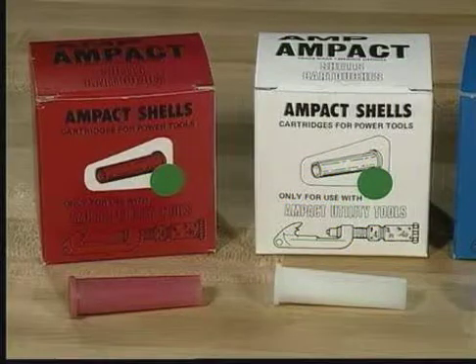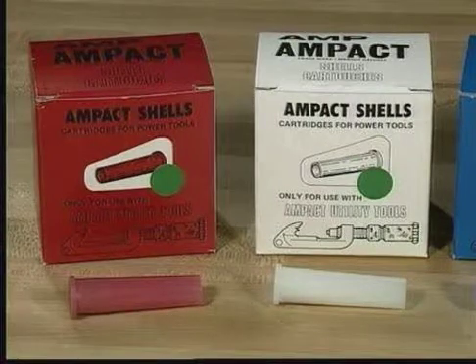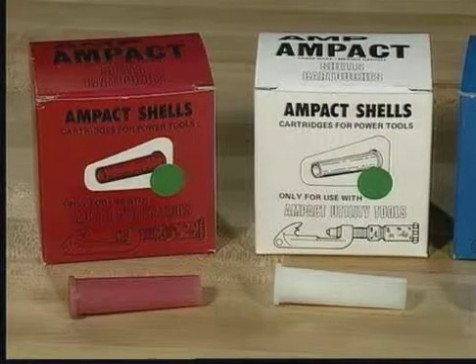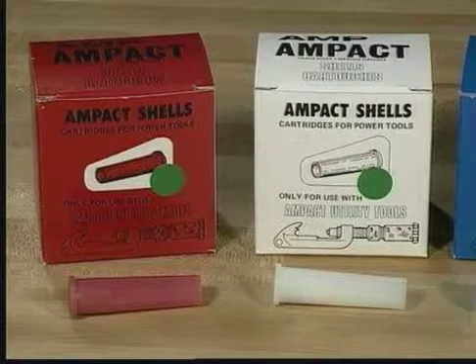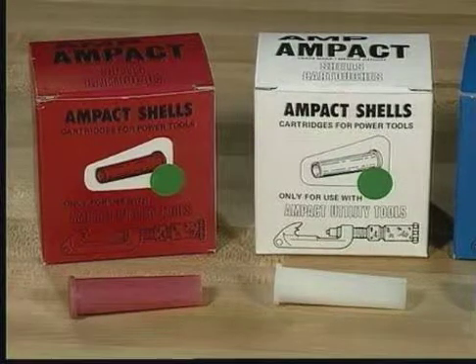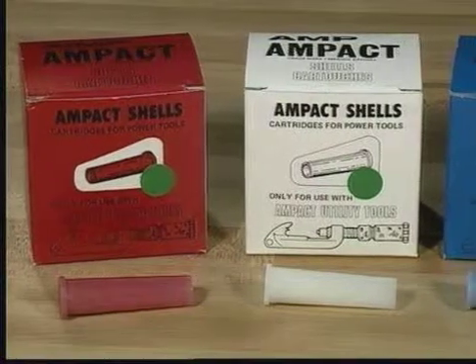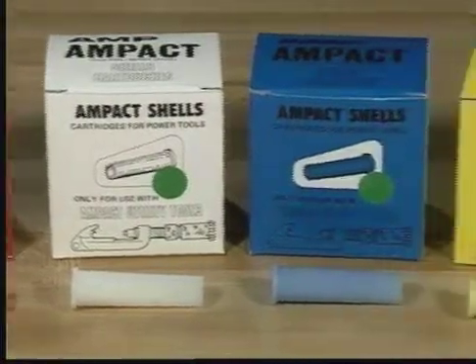The Ampact tap system uses four color-coated shells, each containing a different powder charge. The red, or smaller shell, is used to apply red-coated taps and is used to remove red, white, and blue-coated taps. The white shell is used to apply type 2 and copper taps, but should not be used for removal.